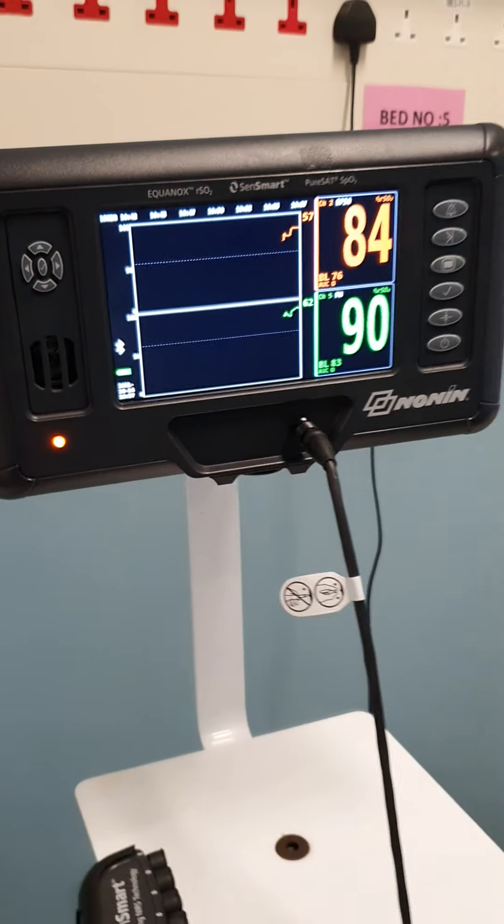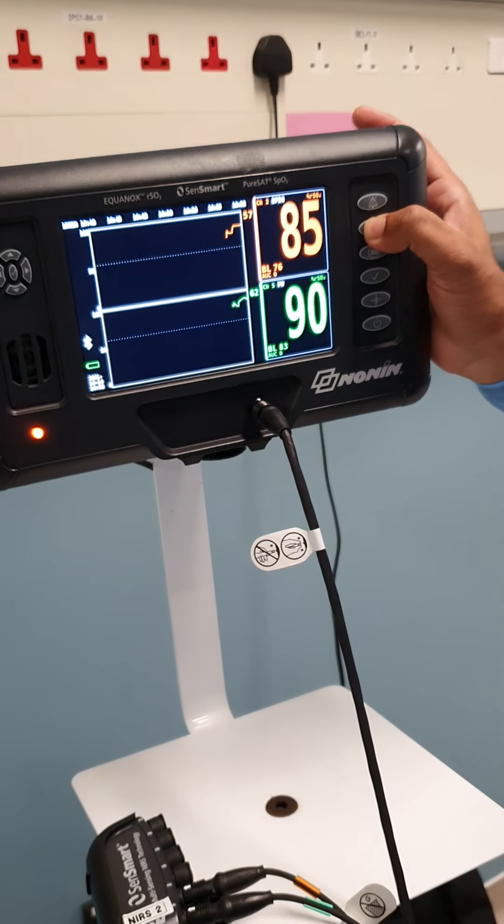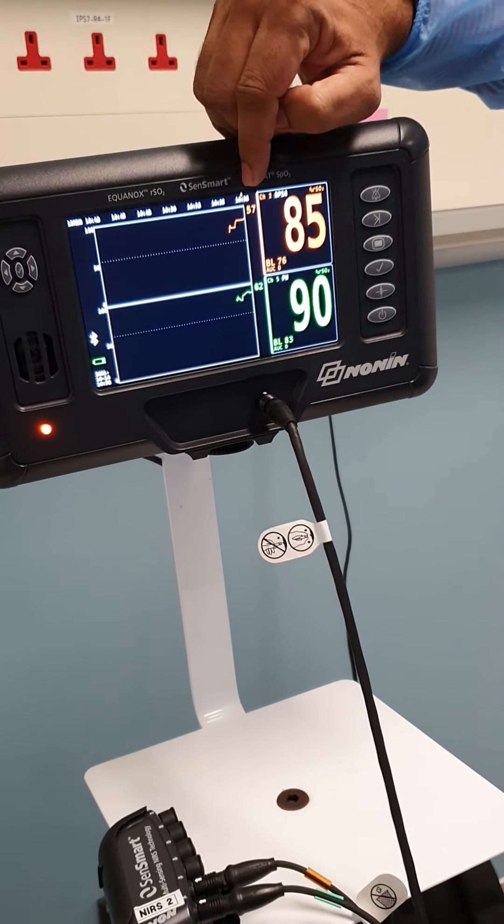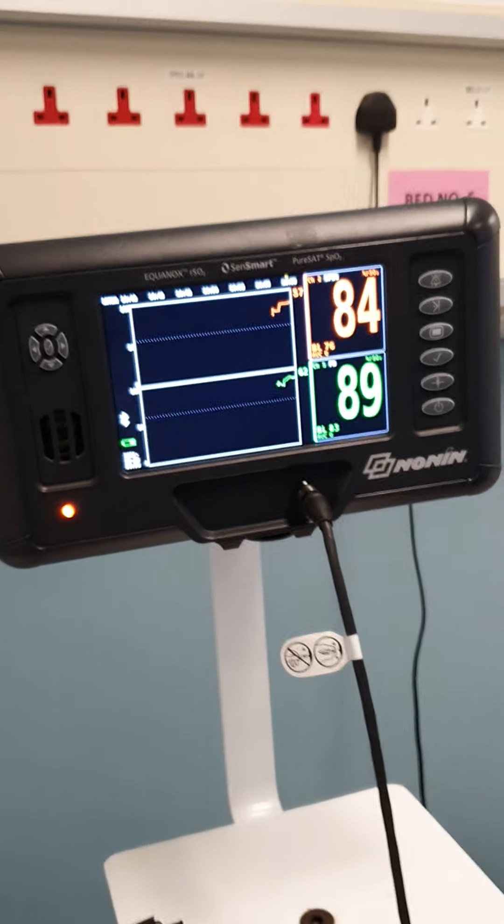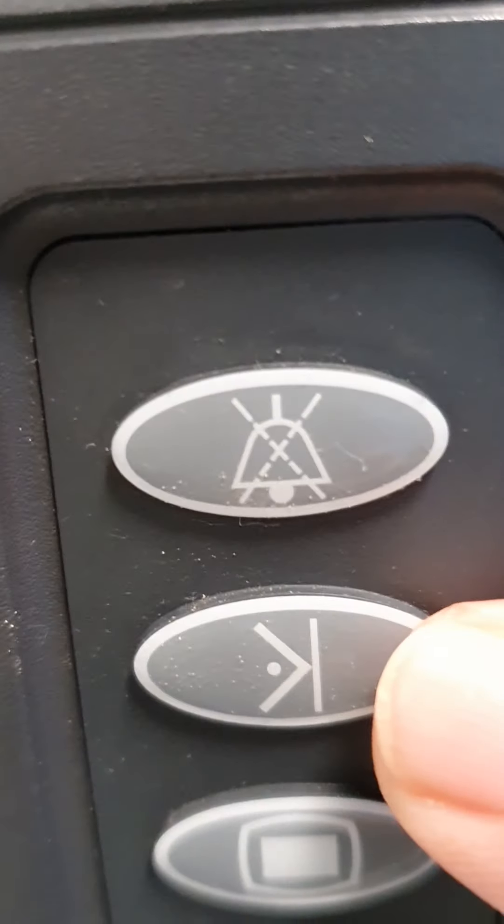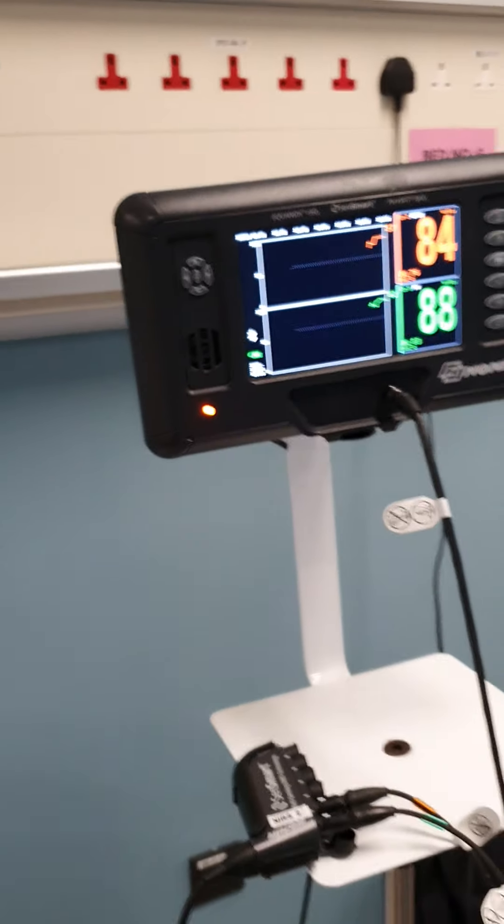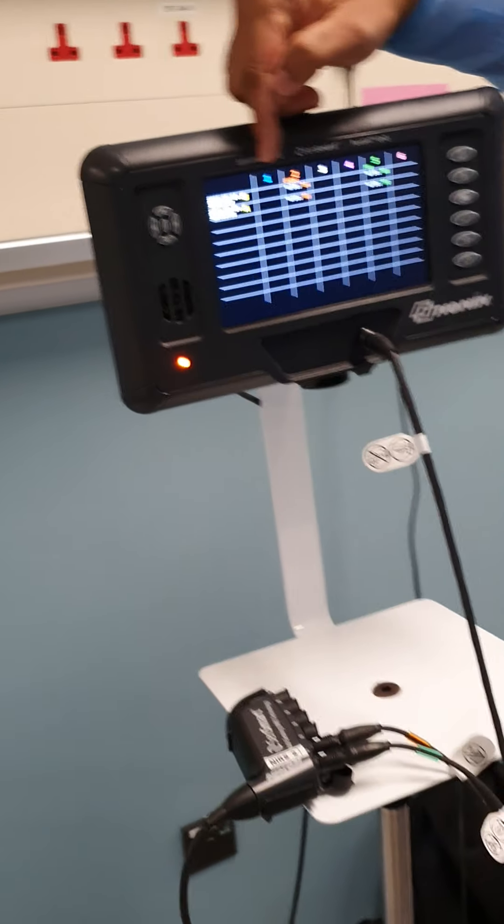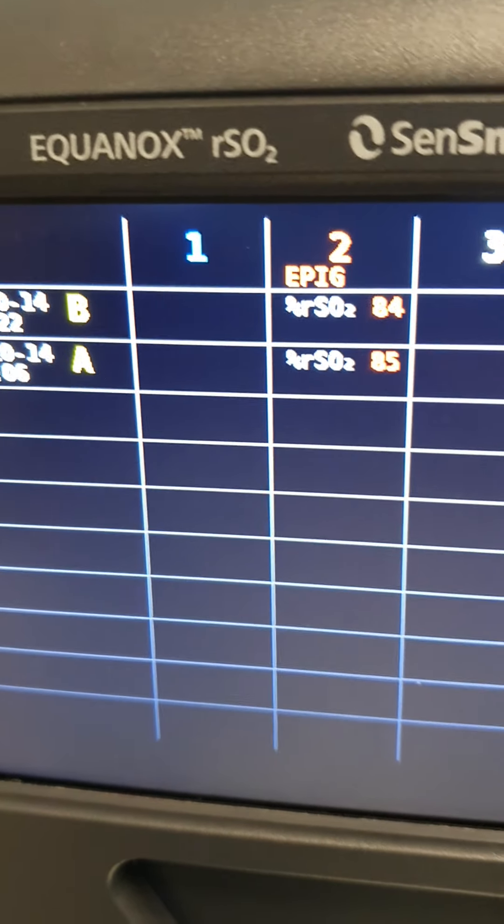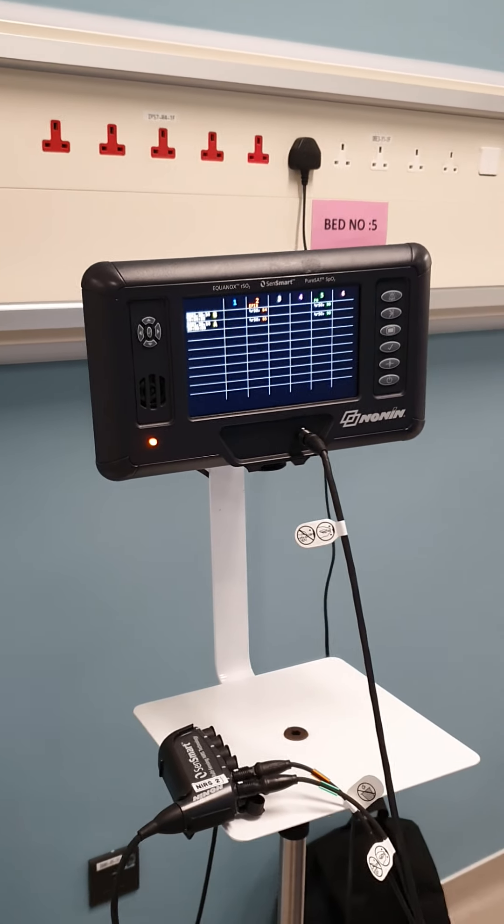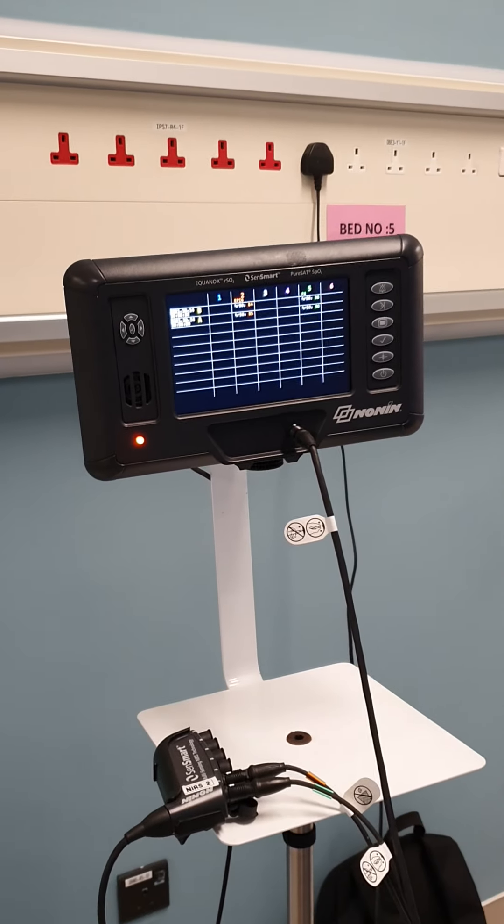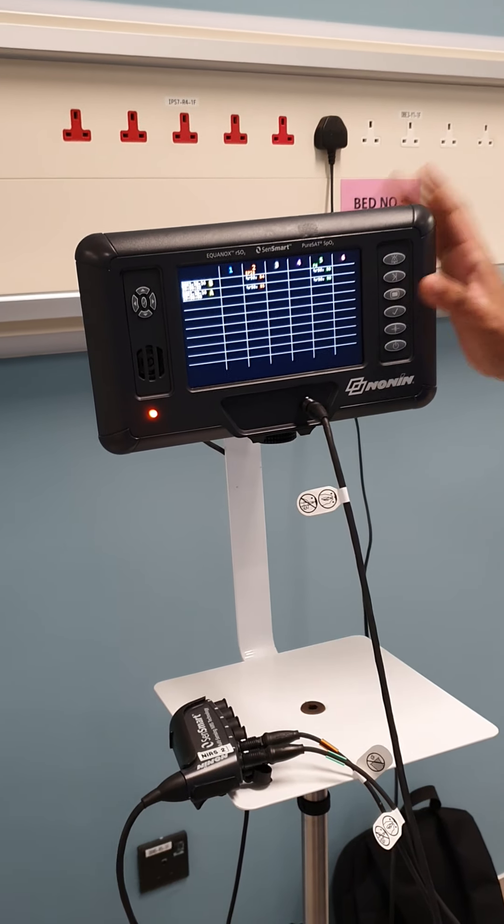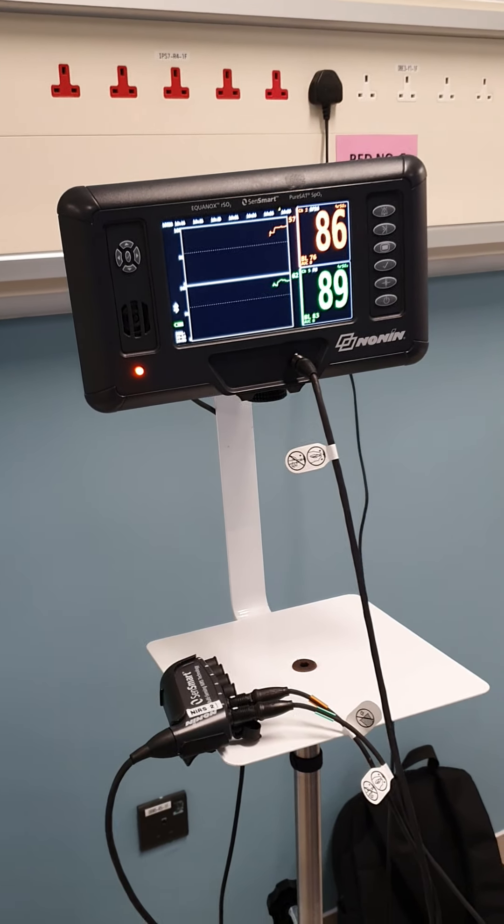One more thing now. If suppose you are not there and a nurse is there, she finds that some event is there which she needs to show to the doctor. What she'll do? She'll just click over here once. Once this is clicked, an event is marked and you can see A over here. That is one event that has been stored in the machine already. So maybe within eight hours she is marking A, B, C, D from this event marker. Now how do I retrieve those events? I'll just keep pressing this for a couple of seconds and you can see I have all the events here. Six events, six channels, whatever events have happened, you have on a single screen. Within 24 hours whatever has happened, you can see with the single screen. Once you want to go back to the main screen, I'll just press this. That's it. It's very simple to use.